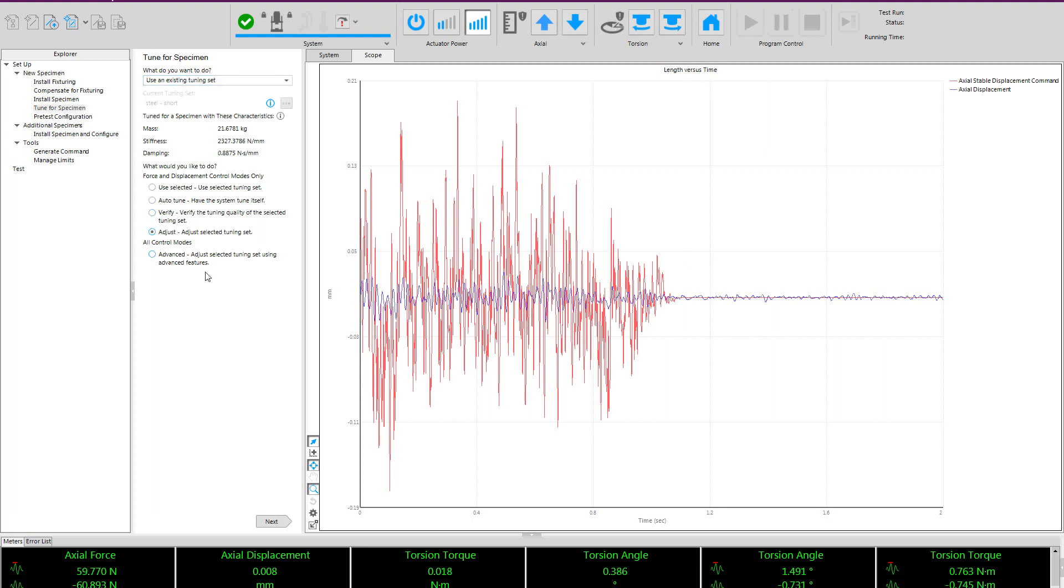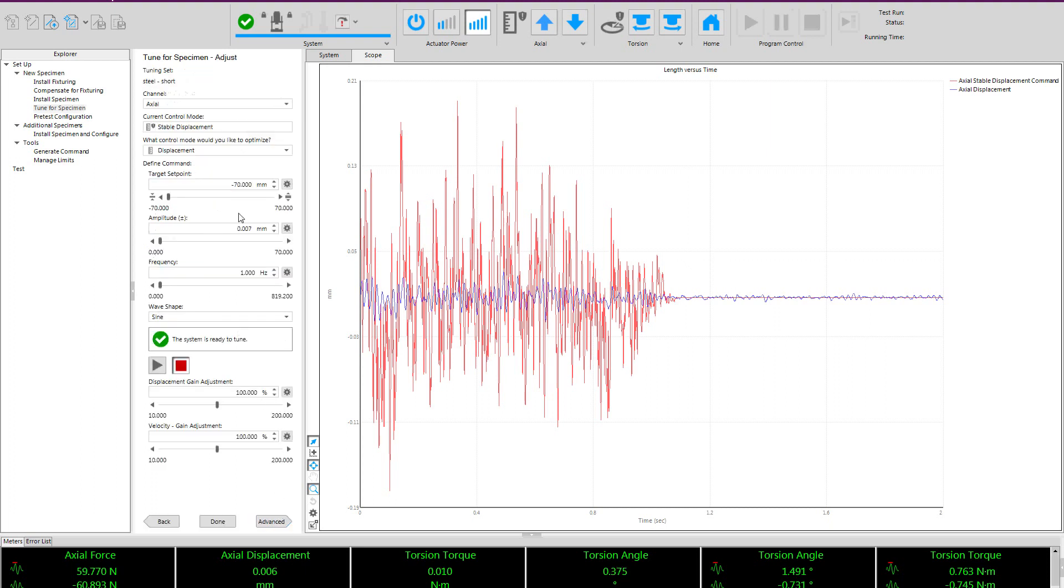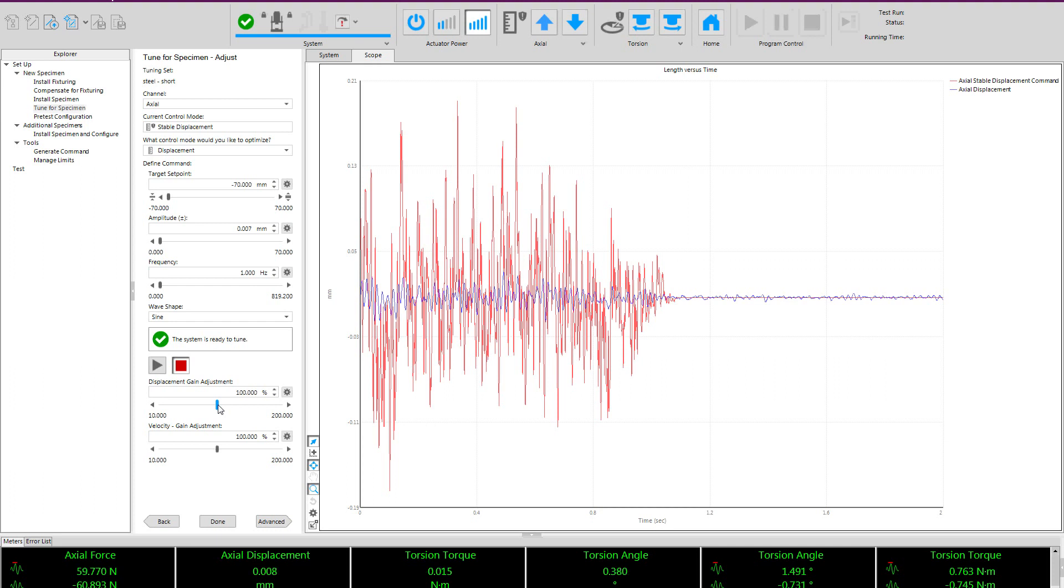I can go into our adjust procedure, which allows me to generate a sine wave or other waveform of choice, and make simple gain adjustments with the slider bar. This is a simple adjustment allowing the user to adjust the values from the auto tuner. This is typically only needed for samples that have very drastically changing characteristics as they are cycled. But it is a nice feature to have.